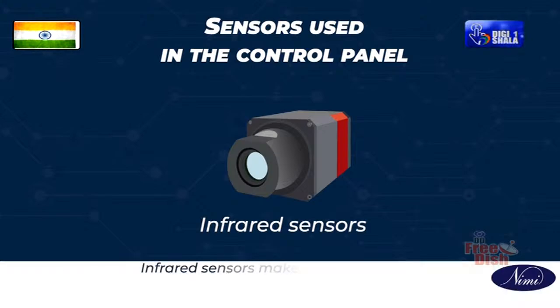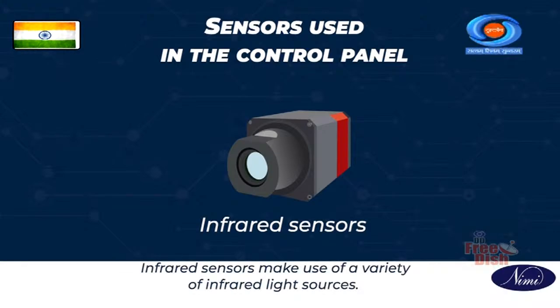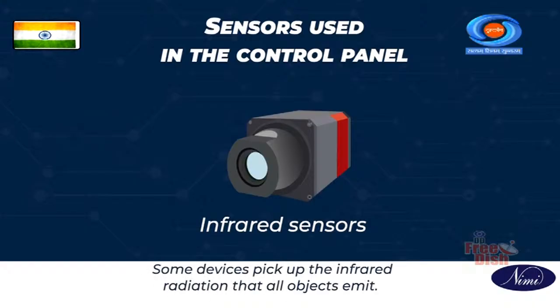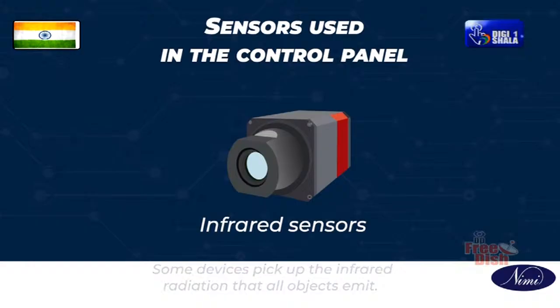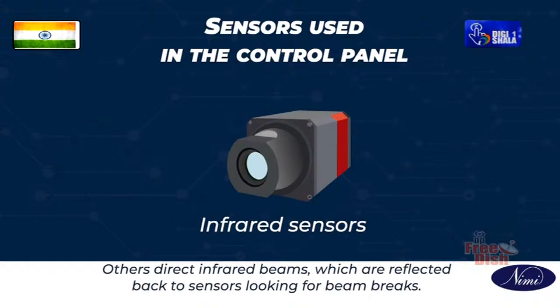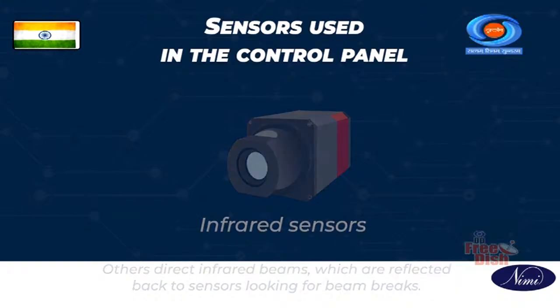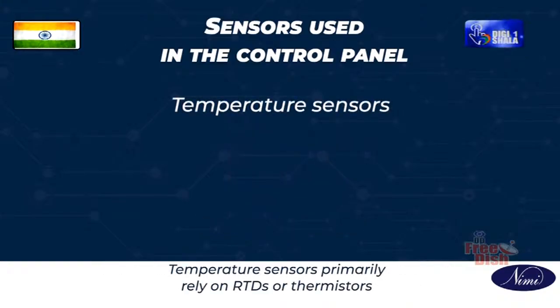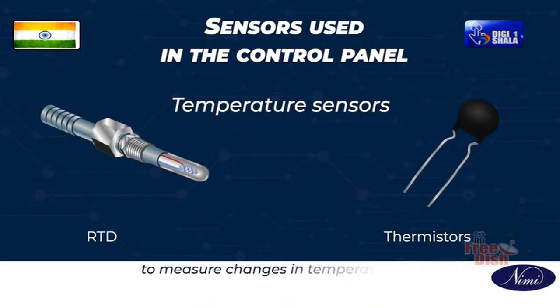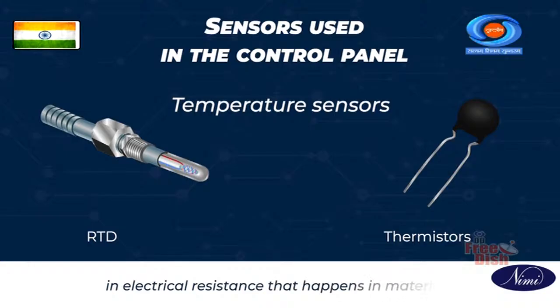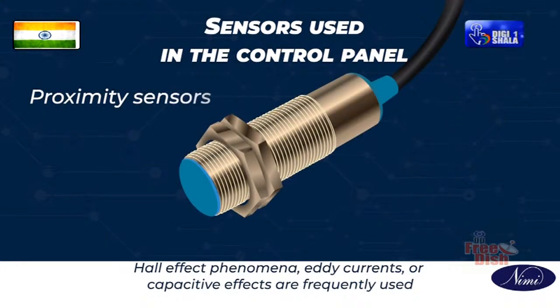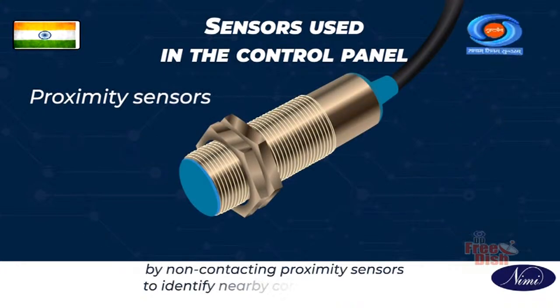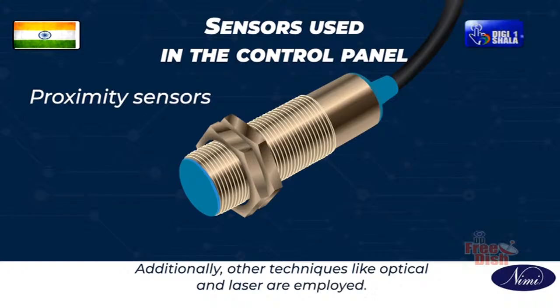Infrared sensors. Infrared sensors make use of a variety of infrared light sources. Some devices pick up the infrared radiation that all objects emit. Others direct infrared beams, which are reflected back to sensors looking for beam breaks. Temperature sensors primarily rely on RTDs or thermistors to measure changes in temperature through the change in electrical resistance that happens in materials. Hall effect phenomena, eddy currents, or capacitive effects are frequently used by non-contacting proximity sensors to identify nearby conductive metals. Additionally, other techniques like optical and laser are employed.